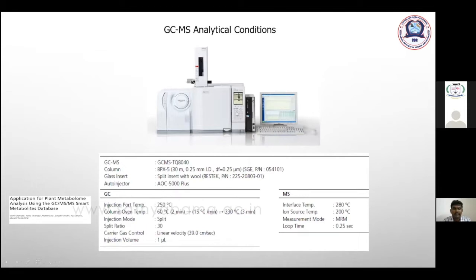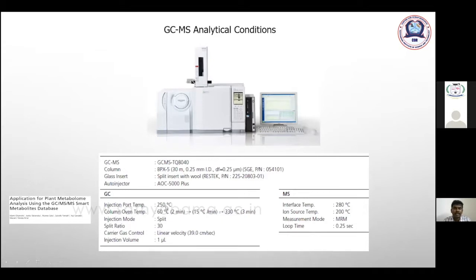The injection port temperature should be 200–300°C so that whatever you inject gets vaporized. The vaporized sample is then pushed through the column. The injection temperature is typically 250°C. For the column oven temperature, a temperature program is used — for example, starting at 60°C, holding for 2 minutes, then increasing at 15°C per minute up to 330°C, then holding at 330°C for 3 minutes.